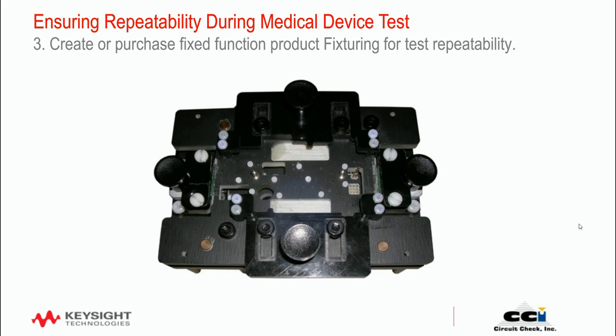It's always good to have a repeatable test setup for the DUT to measurement instrumentation. If not, it's very difficult to show in your design history file the repeatability of RF coexistence measurements. With other types of measurements you typically can create a record, but with RF it's much more difficult.